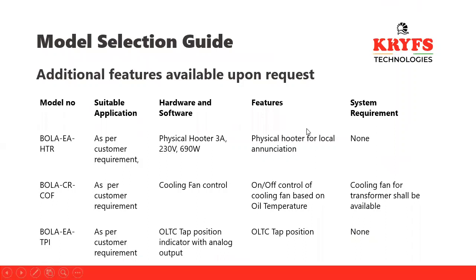So now this was the three varieties of BOLA, and there are a lot of customizations all around. But we have identified some of the customizations which are common requests from the customers. So that is mentioned here. If you want a physical hooter on site, then that hooter can be provided. If you want cooling fan control or cooling pump control or any other control function, that is available at additional cost. OLTC Tap position indicator with analog output, that one is also available at an additional cost.